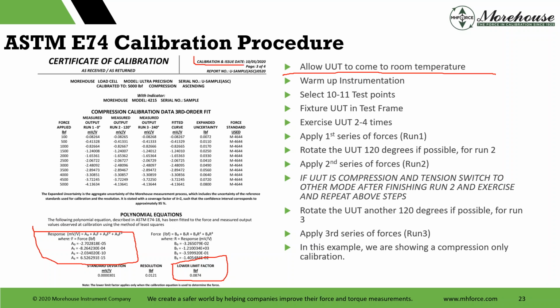So see this right here? That's calibration and issue date. That is now required if you're accredited to the 2017 standard. So we're going to allow it to come to room temperature. It could be 1 day in the lab. It could be 3 days in the lab. If it's a big 2 million pound load cell, we really want 3 days in the lab. If it's a 100-pound load cell, 1 day, 24 hours.